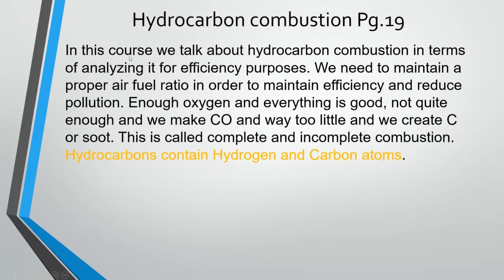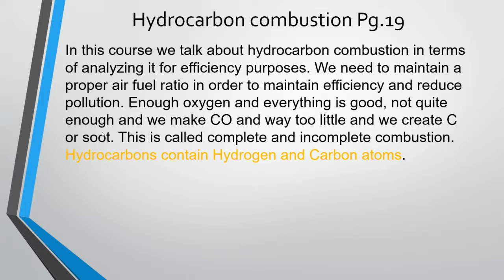In this course we discuss hydrocarbon combustion in terms of analyzing it for efficiency purposes. We need to maintain a proper air-fuel ratio to maintain efficiency and reduce pollution. Enough oxygen and everything burns well. Not quite enough oxygen and we produce carbon monoxide, which is very harmful. Way too little oxygen and we create carbon or soot — undesirable visually and environmentally. Monitoring combustion by measuring oxygen and carbon monoxide is how we maintain proper operating efficiency.